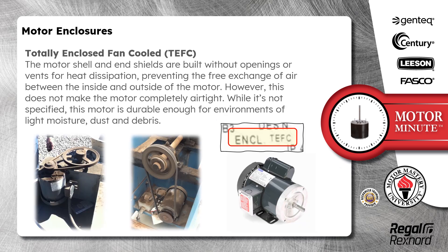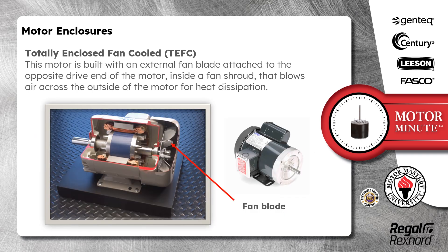Totally enclosed fan cooled, TEFC. The motor shell and end shields are built without openings or vents for heat dissipation, preventing the free exchange of air between the inside and outside of the motor. However, this does not make the motor completely airtight. While it is not specified, this motor is durable enough for environments of light moisture, dust, and debris. TEFC motors are built with an external fan blade attached to the opposite drive end of the motor, inside a fan shroud that blows air across the outside of the motor for heat dissipation.